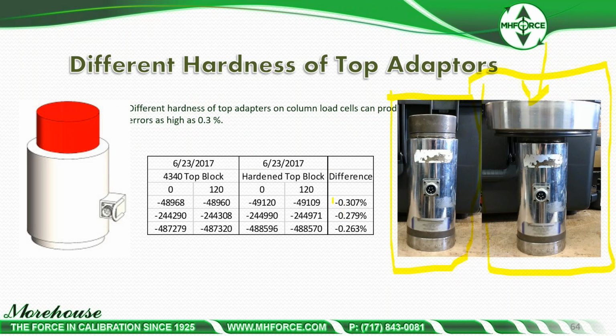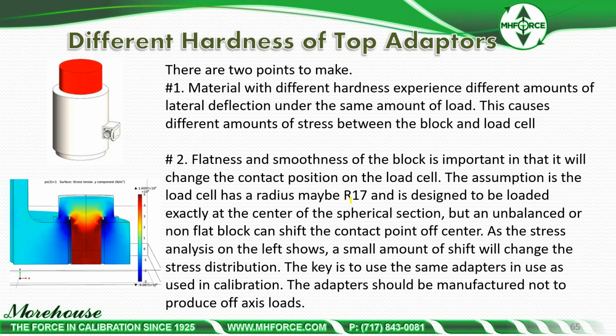But this example, look at these differences. Same day calibration, same load cell. I did this over multiple days, different top blocks, tested R&R, and at the end, you can see these different top blocks change the output by as high as 0.3%, just because of the hardness. And you could say, how is that? And these are the 2 points we need to make. Material with different hardness experience different amounts of lateral deflection under the same amount of load. This causes different amounts of stress between the block and load cell.